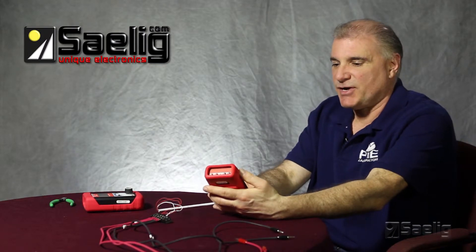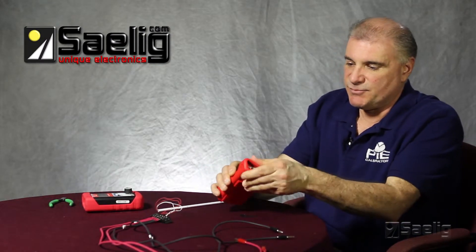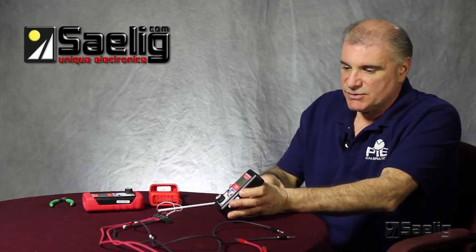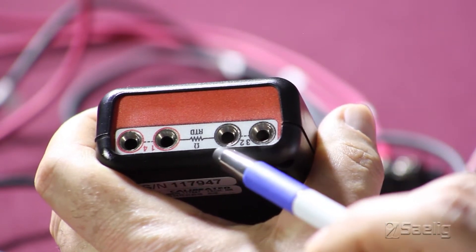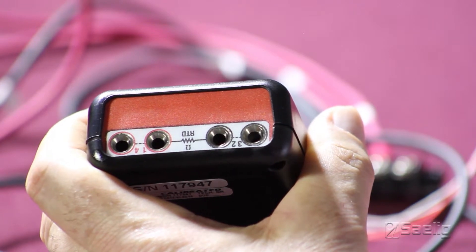Like other PIE calibrators, connections are made in the back of the calibrator. I'll remove the boot here just for ease of viewing. We'll be using a 4-wire RTD. As you can see, wires 1 and 4 and 2 and 3 are marked on the back of the calibrator, and we'll just make sure that our RTD sensor is connected correctly.